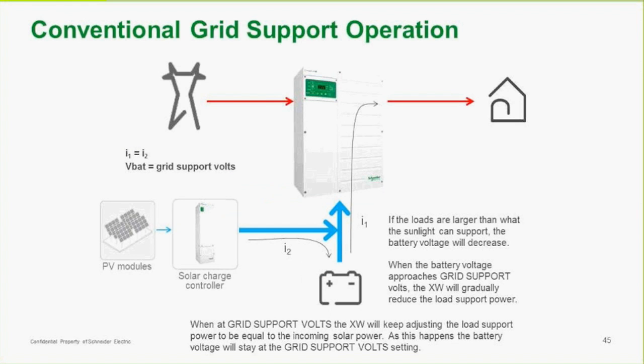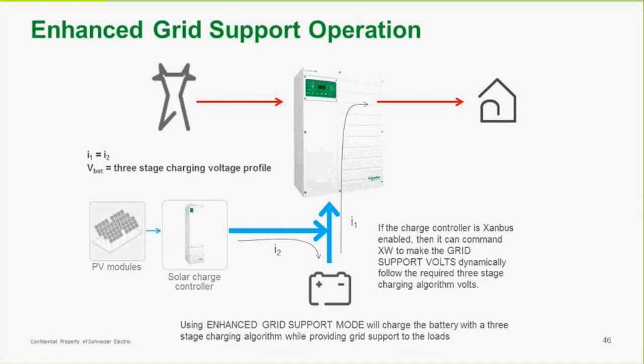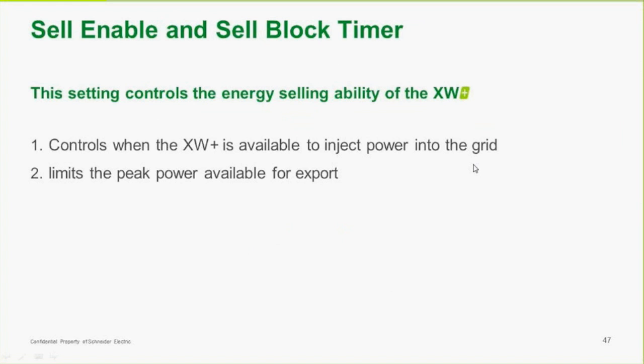In a conventional grid support operation, what we have here is PV modules and the solar charge controller. And as you can see, we're supplying power to the loads. When the battery voltage approaches the grid support volts, the XW will gradually reduce the load support power and start picking up more from the grid. Now, to enhance grid support, again, we're taking care of the battery first. So the battery maintains a high state of charge, and any excess power is used to support the grid.